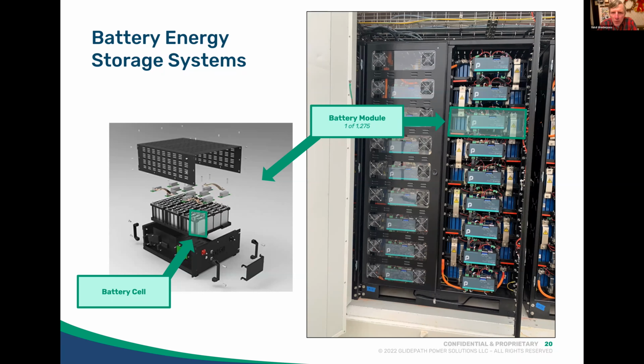You've got hundreds of these small fans on each module rack that plugs into this huge rack, or drawers that plug into the rack. Are each of these individual fans monitored in case they fail? There's probably a chance of dust too, maybe a filter. Do you monitor for that, or does somebody manually check to make sure filters get replaced or cleaned out? And do you heat these battery systems during a cold spell, like minus 20 degrees? Do you have heating capacity to keep thermal conditions optimal for the whole battery system?